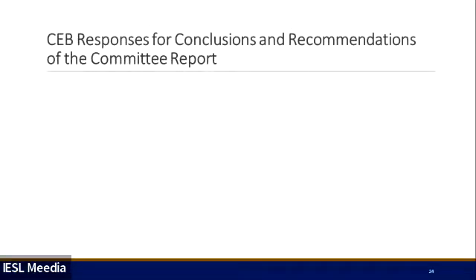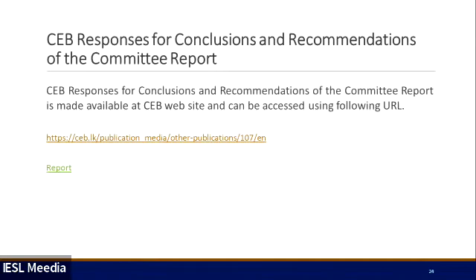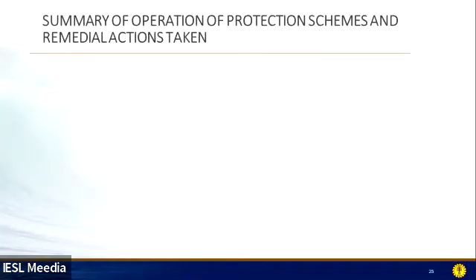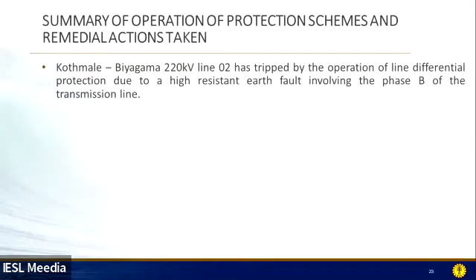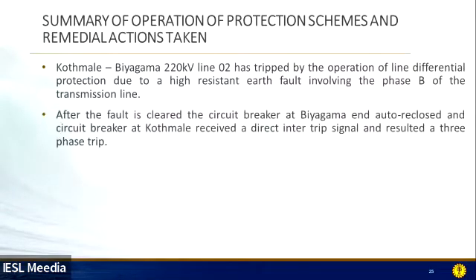The CEB response for conclusion and recommendation of the committee report is available in the following location. Summary of operational protection schemes and remedial action taken by CEB. Kotmale Biagama 220kV line 2 tripped by the operation of line differential protection due to a high resistance earth fault involved in phase B of the transmission line. After the fault was cleared, the circuit breaker at Biagama auto-reclosed and the circuit breaker at Kotmale received a direct inter-trip signal, resulting in a 3-phase trip.